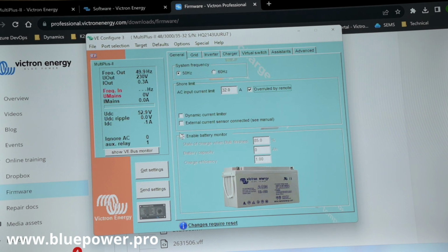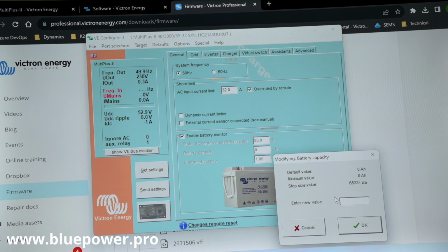Next we've got our battery monitor. That's the built-in battery monitor of the inverter. It gives the inverter the capability to work out more or less where the battery state of charge is at a given moment. If you don't have a GX device connected, then the inverter is never going to know or have an updated value of the battery state of charge. So it's required to set this exactly according to the battery manufacturer specs so that you can have an accurate indication of state of charge. Not perfect.